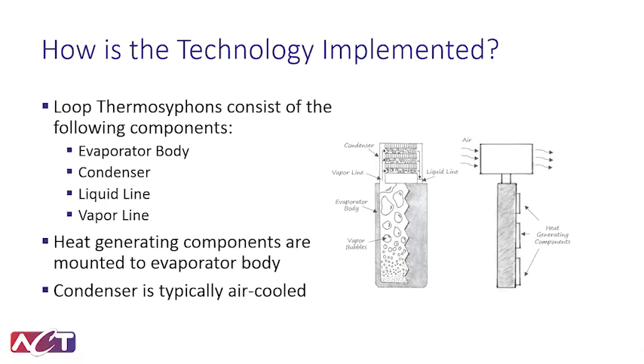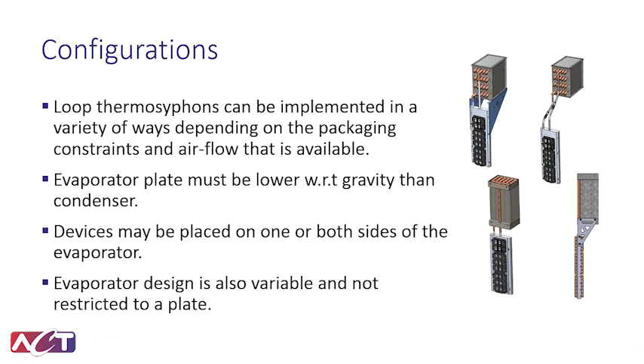The evaporator and condenser can take on really any form. It could be a flat plate, a liquid to liquid heat exchanger, or an air to air heat exchanger — whatever is necessary. The only requirement is that the condenser is physically above the evaporator so you have gravity working in your advantage. Different configurations of the loop thermosiphon have been built here at ACT. You can remotely mount the condenser as shown in the top right image, and use flexible lines that give the system designer a lot of flexibility. You can blow air from top to bottom or left to right — there's really an infinite number of ways to configure these systems to fit your needs.